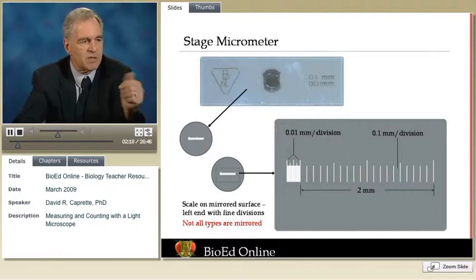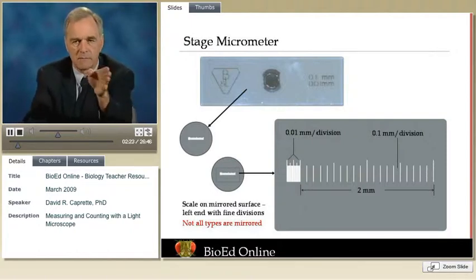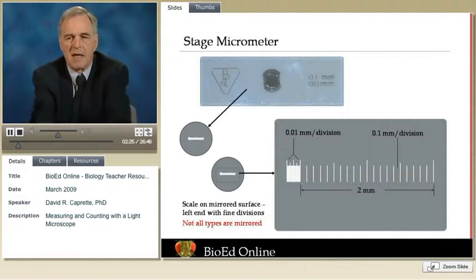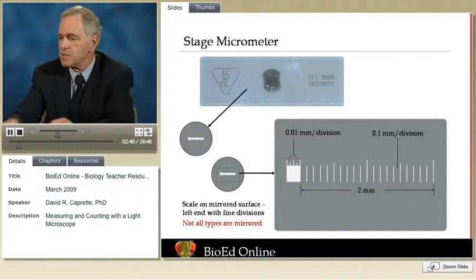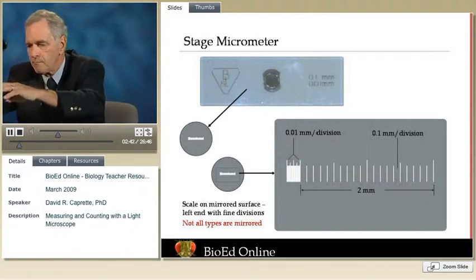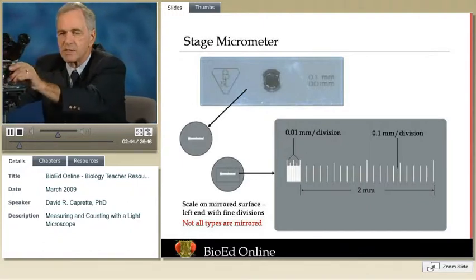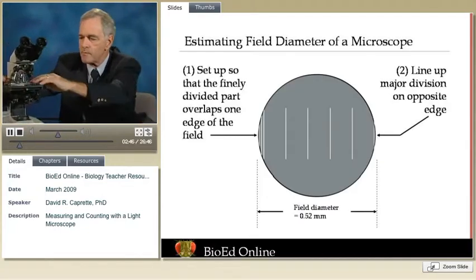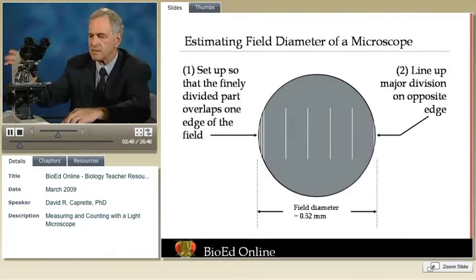It would have divisions of a tenth of a millimeter distance per division, and then one end might be subdivided into increments of 0.02 millimeter, or maybe even 0.01 millimeter, 10 micrometers, which is pretty tiny. To use a stage micrometer, we can use it in a number of ways. We can use it to calibrate an eyepiece reticle. We can also use it to estimate field diameter.